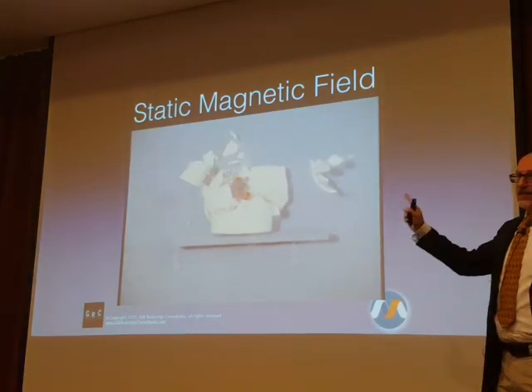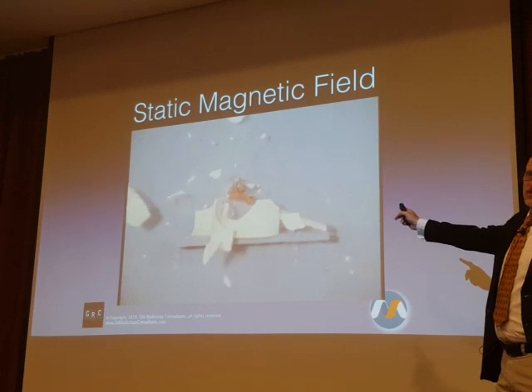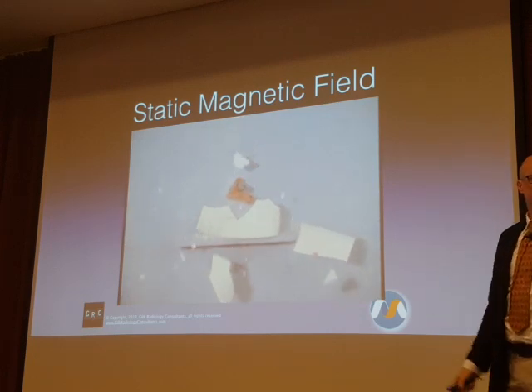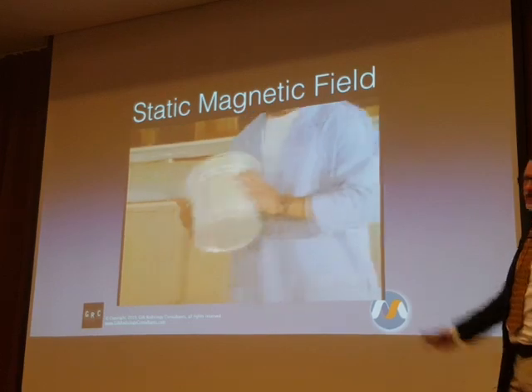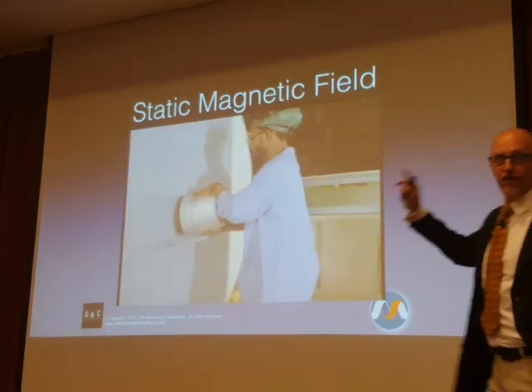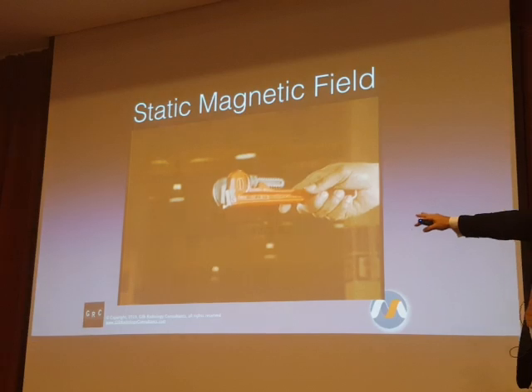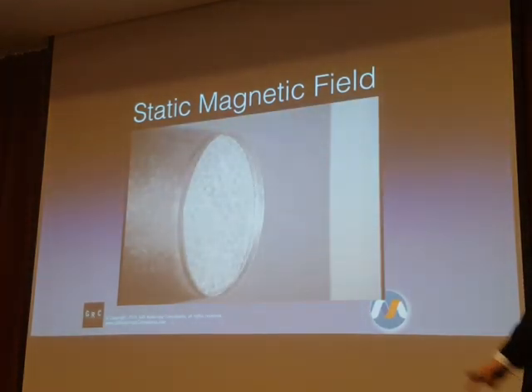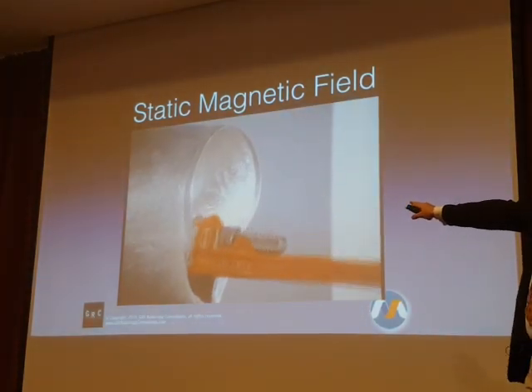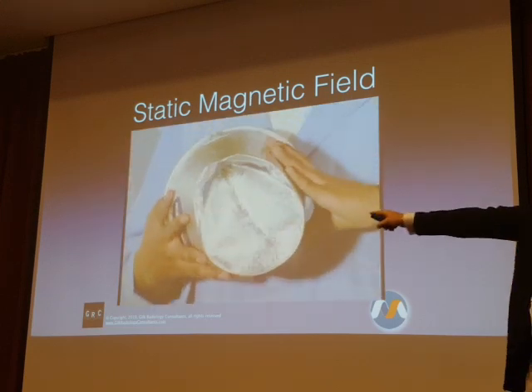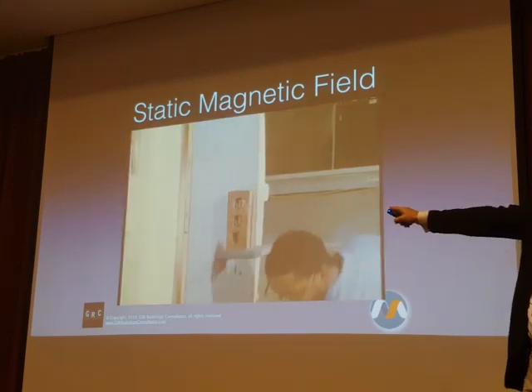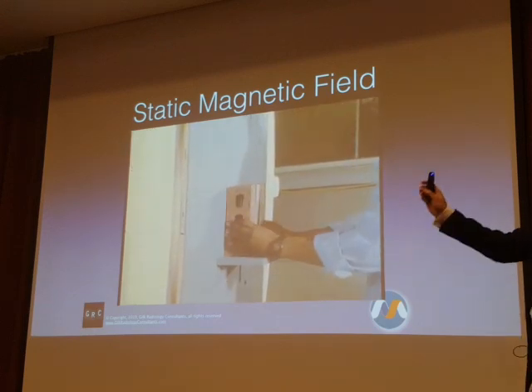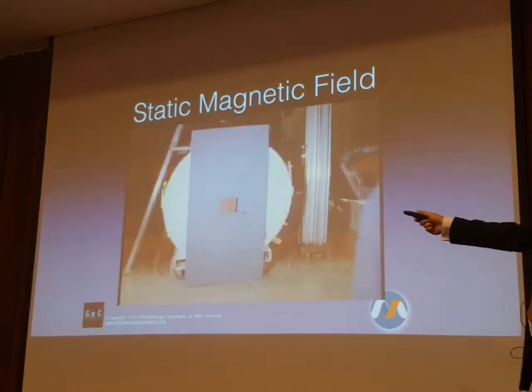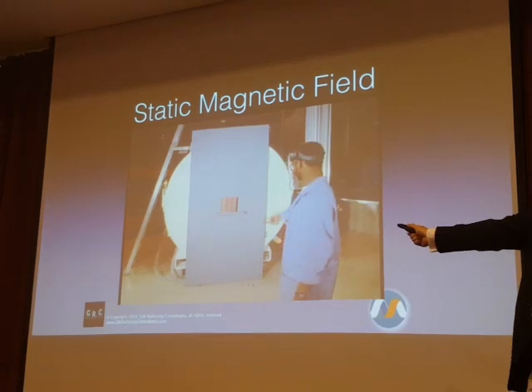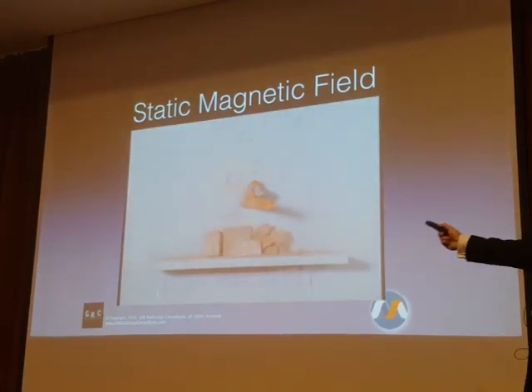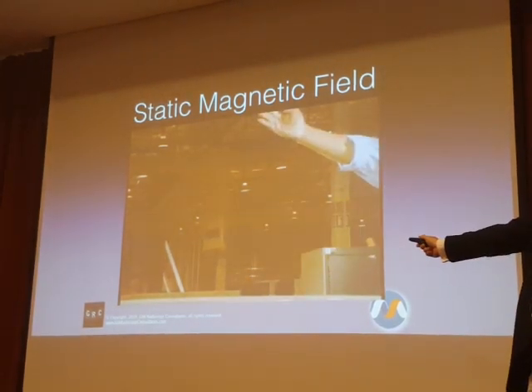So this is what the static magnetic field from a safety standpoint is really known for. This is an excerpt from a GE safety video that's probably 20, 25 years old at this point. It's a wrench that weighs maybe a kilogram. This is an old 1.5 Tesla GE magnet. I think this is one of their S2 or S3 magnet systems that had very poor active shielding.